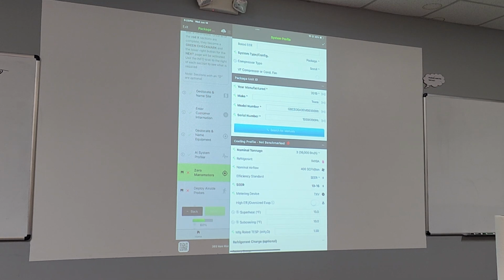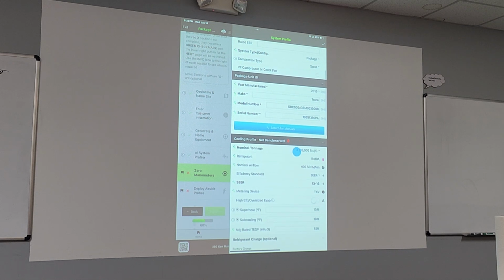So make sure you check that box, and if it's a modulating system, it has to be tested on full speed. When you tell it that it's a 3-ton unit down here, we're expecting that unit to be trying to run at 3 tons. If it's modulating and jumping up and down, MeasureQuick has no way of knowing what the controller is trying to achieve, so it can't tell if it's doing a good job or not. So we got to have it in charge mode or test mode.